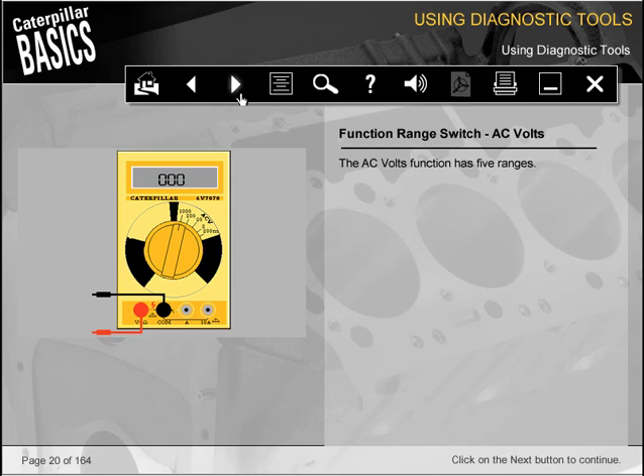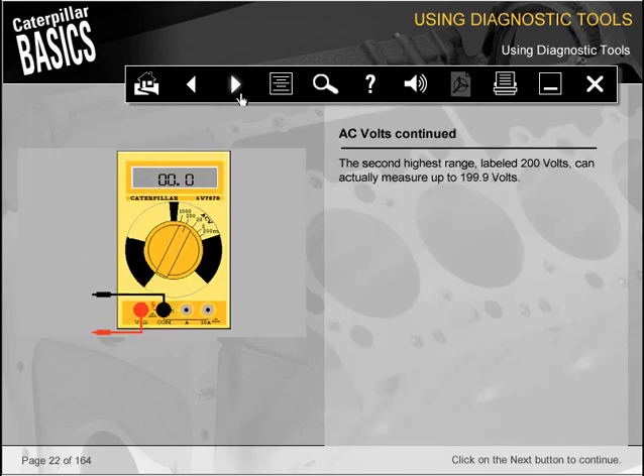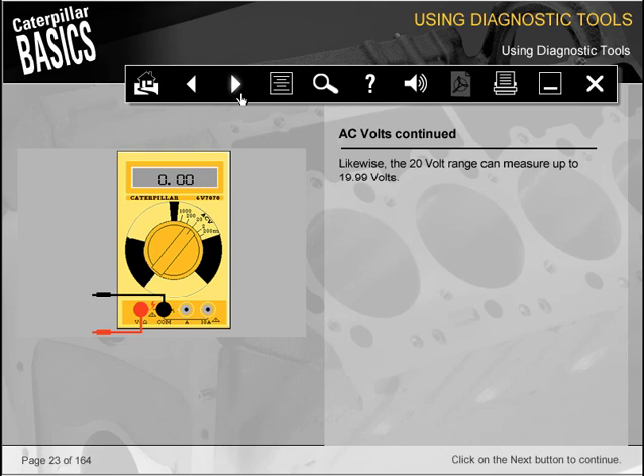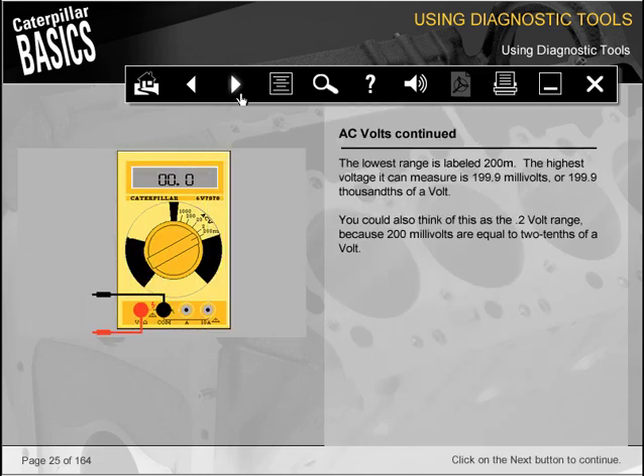The AC volts function has 5 ranges. The 1000 volt range is highest and can measure up to 1000 volts AC. The second highest range, labeled 200 volts, can actually measure up to 199.9 volts. Likewise, the 20 volt range can measure up to 19.99 volts. The 2 volt range can measure up to 1.999 volts. The lowest range is labeled 200m. The highest voltage it can measure is 199.9 millivolts, or 199.9 thousandths of a volt. You could also think of this as the 0.2 volt range, because 200 millivolts are equal to 2/10 of a volt.